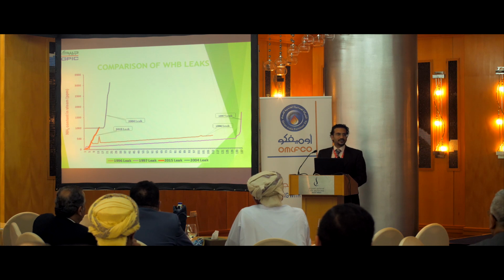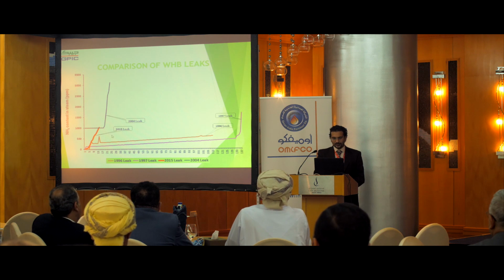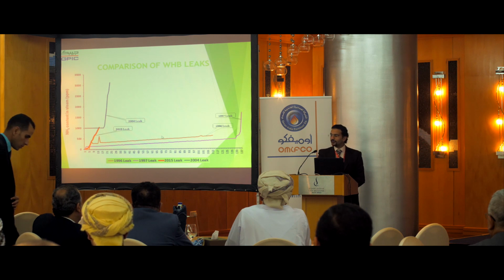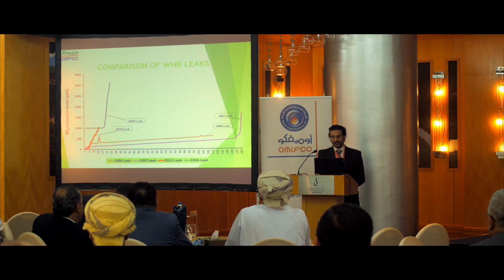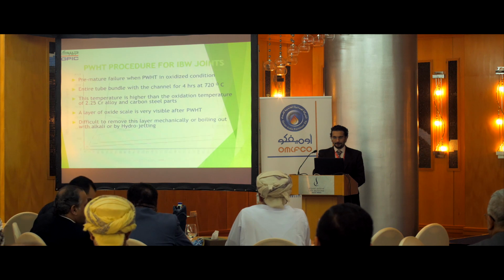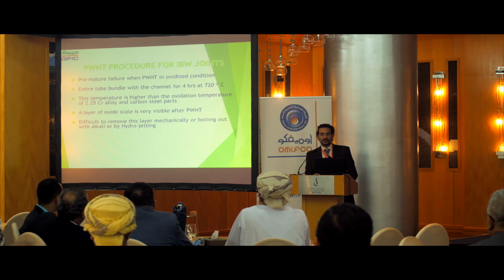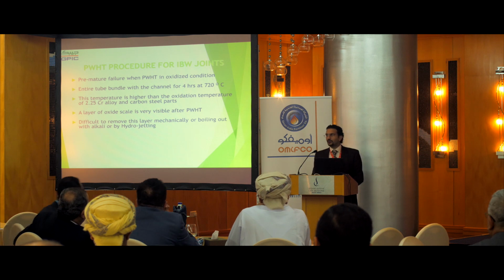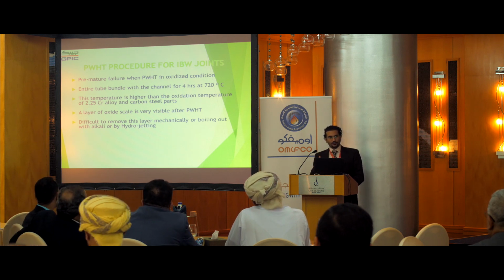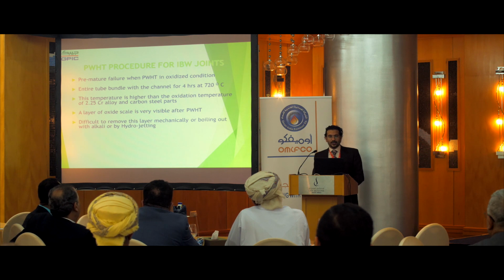And this is the recent leak compared with the other waste heat boiler leaks. The 2015 leak failed after only 6 months in service. However, the others could be controlled; the tubes were plugged until we had to replace them. The post-weld heat treatment for the IBW joints of our earlier waste heat boilers led to premature failure when the post-weld heat treatment was done in oxidized condition.